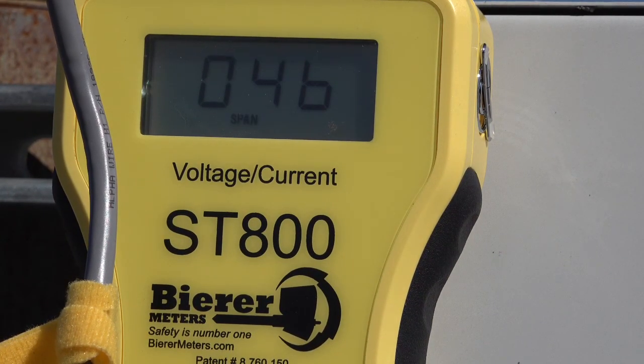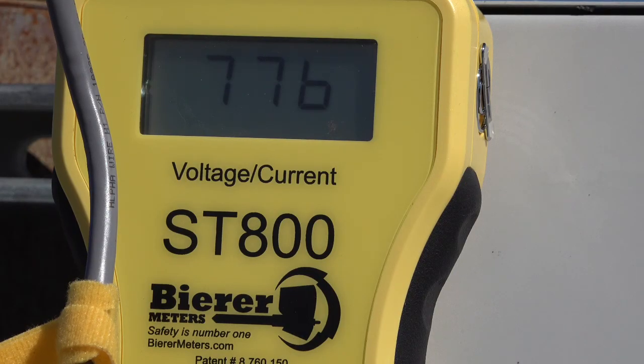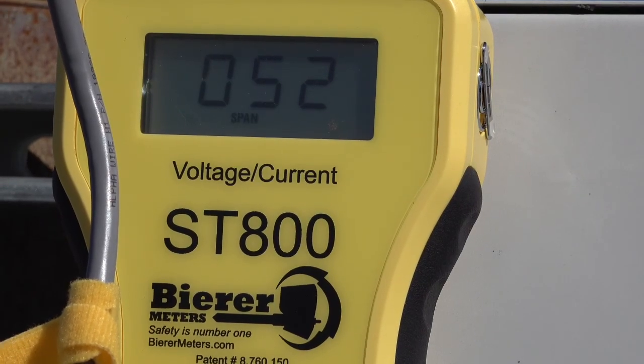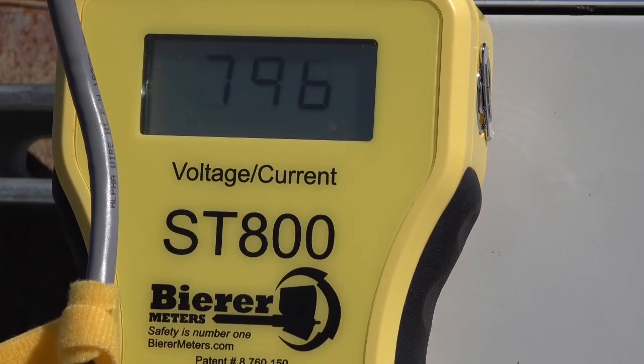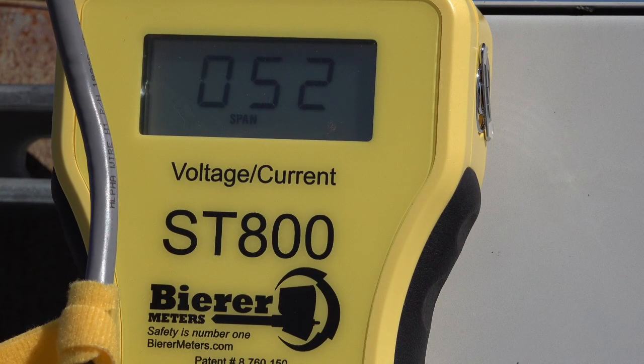This is obviously a good service that we're attached to in this demonstration, and at approximately 50 counts we're already up close to 700 amps. Now let's let the ST800 continue up to 800 amps and talk about how high the count number is and what that means. We'll notice it stopped at 52 counts at 800 amps. So the first thing we noticed on this service was that the ST800 was able to achieve a much greater than 8 amp per count increase. The other thing we noticed is the count number itself, stopping at 52.